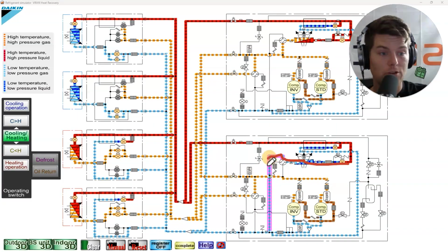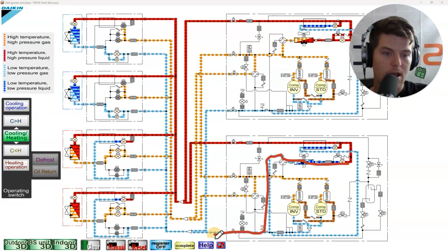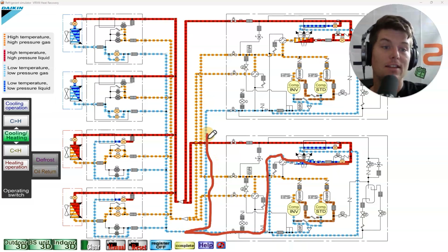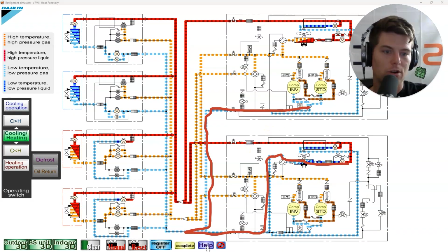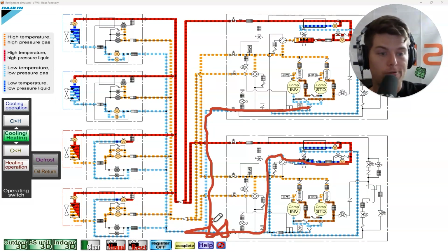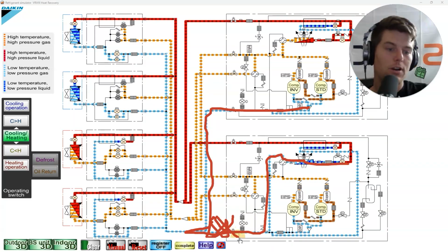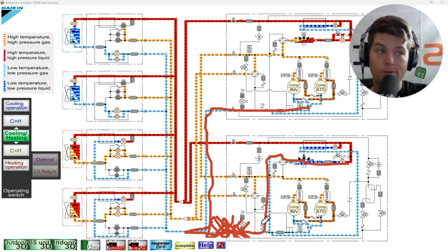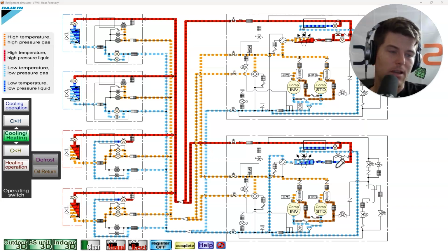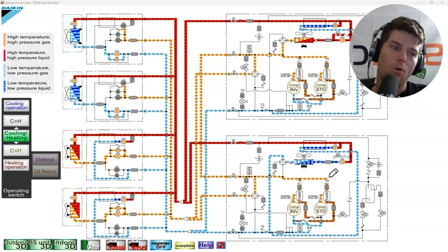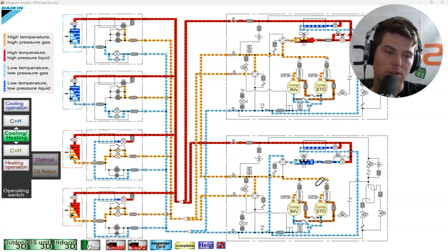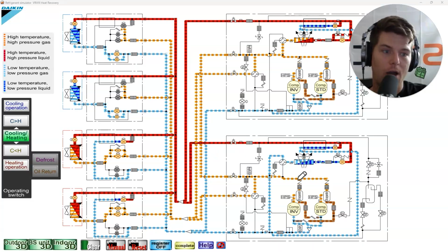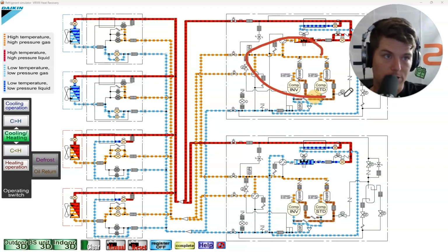And the reason we can measure that is because, 1, we compared it to TE, but also we can see that it doesn't rise up to ambient temperature. There should be 0 refrigerant flowing through this line right now. This unit should have no refrigerant flowing through it. It should be at ambient temperature, and it never hits that except for when this module goes into some kind of demand, allowing it to do exactly what this module is doing up here.